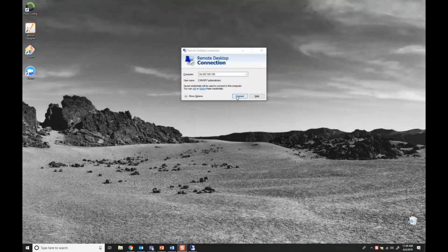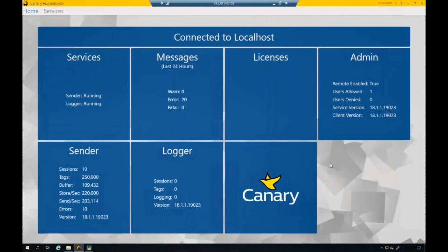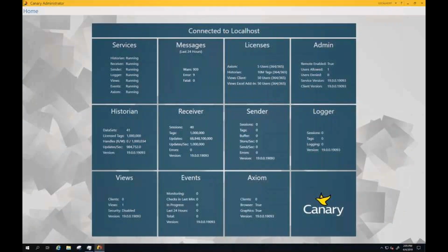Yeah. So for this short demo, Carl, one of the principal engineers from the US, showed us an example of installing the collector into a sender environment, like the OPC server environment. They installed this at an oil and gas customer. They tested with 4 different loggers from 4 different sites with 4 different OPC servers. So the logger is mining about 250,000 tags from the OPC server. Yeah. So this is averaging between 270 to 250 in a way.